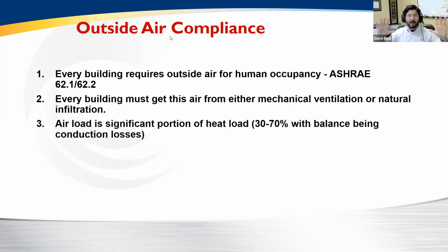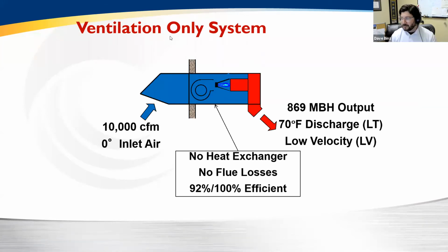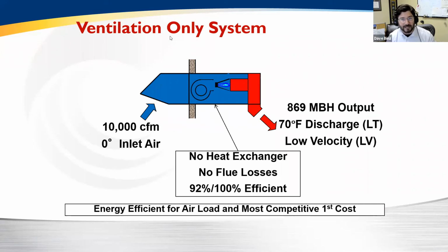So if you think about it, how can it be energy efficient to utilize outside air? The first thing is that every building gets outside air and we have to heat it somehow. So let's look at the most energy efficient way to heat our ventilation requirement. Let's take an example of a building that has a 10,000 CFM exhaust, and we take our 0 degree outdoor ambient condition, and I've got to heat that up to 70 degrees, or whatever my indoor design temperature is. With a direct fired 100% outside air system with no heat exchanger and no flue losses, I have the most combustion efficient technology available to heat my ventilation. So if I'm looking at the most energy efficient way to heat the air load, it's going to be utilizing a 100% outside air direct fired unit.